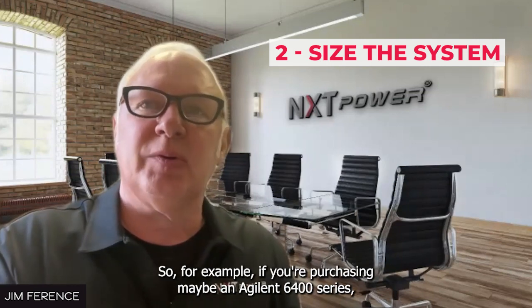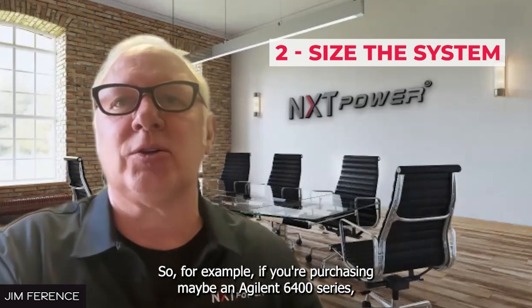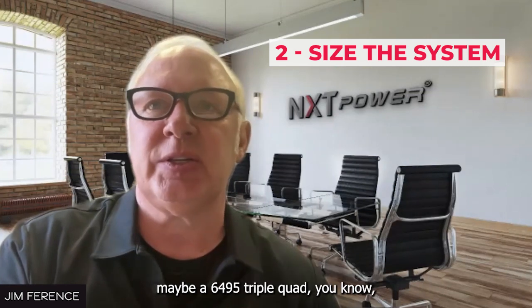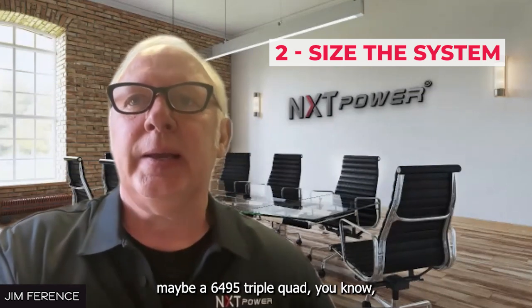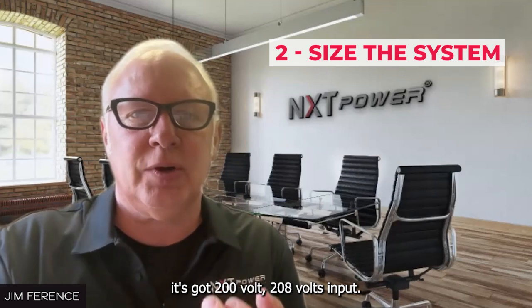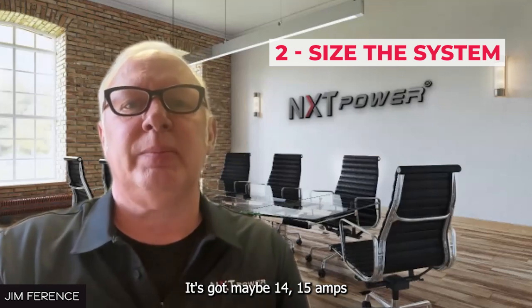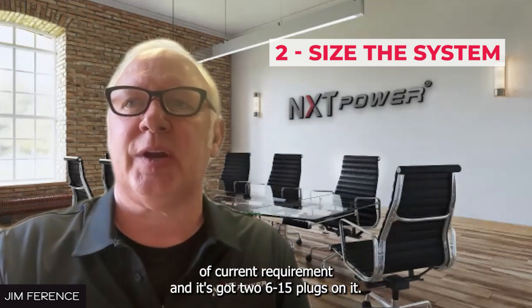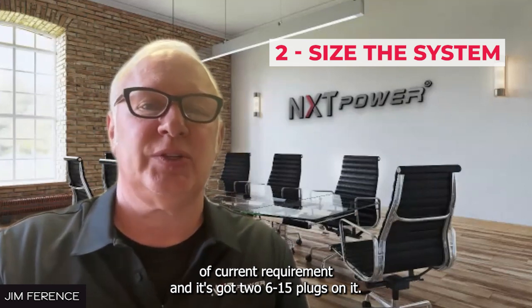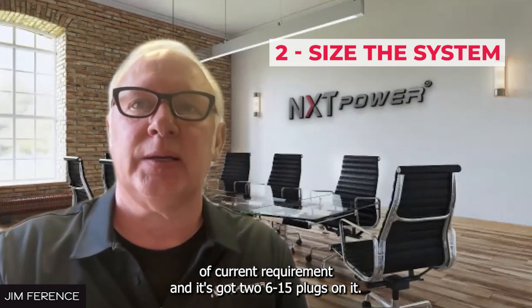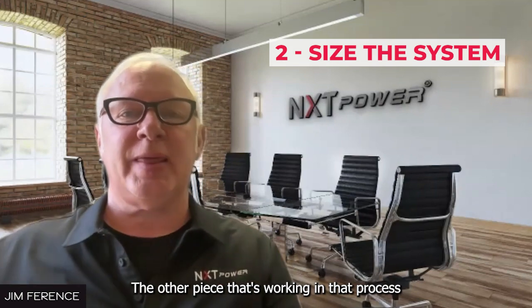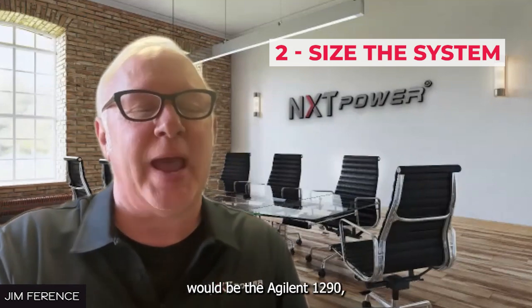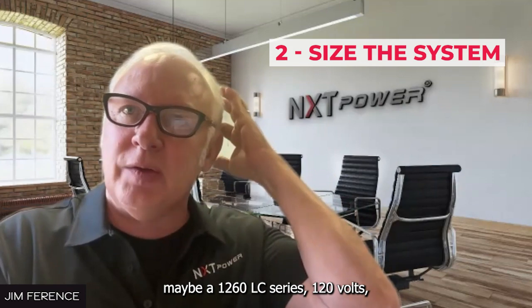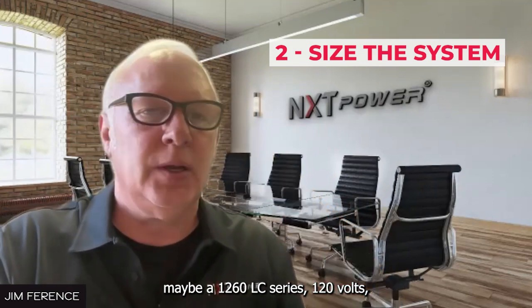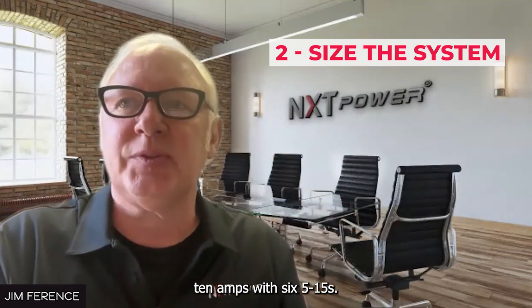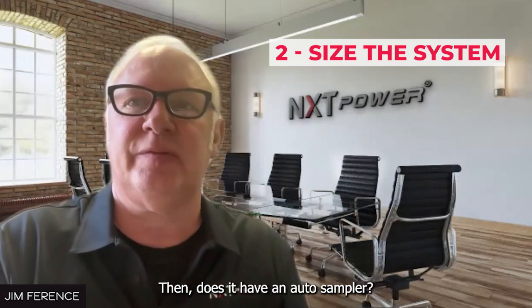For example, if you're purchasing maybe an Agilent 6400 series, say a 6495 triple quad, it's got 208 volt input, maybe 15 amps of current requirement, and two 6-15 plugs on it. The other piece working in that process would be the Agilent 1290, maybe a 1260 LC series, 120 volts, 10 amps, with 6 5-15s.